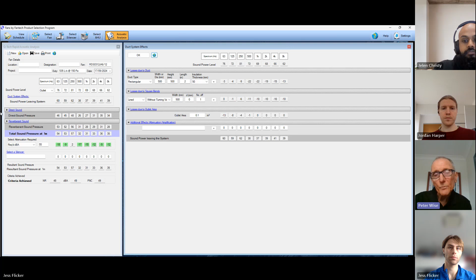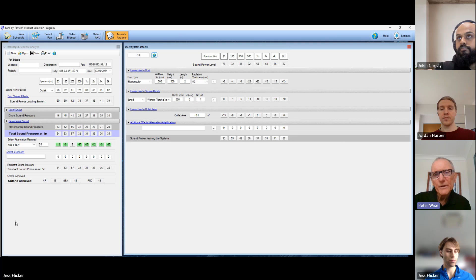I'm not an acoustic specialist, don't get me wrong, but I have had a lot of experience over the years, and it is a big topic. This is why I'm probably harping about it a bit - to be aware of it and always have a good look at it. Because you get to a stage where you say, no, we don't need to worry about this system, that fan's going to be fine. Then some you might think, oh, it might be a bit borderline, perhaps we should do a calculation, or perhaps we just put in some internal lining after the fan, which has been done. I'd say in your case, Jordan, they probably didn't do a calculation - they probably thought, oh, we'll just put some internal lining in the ductwork here and that should do it.